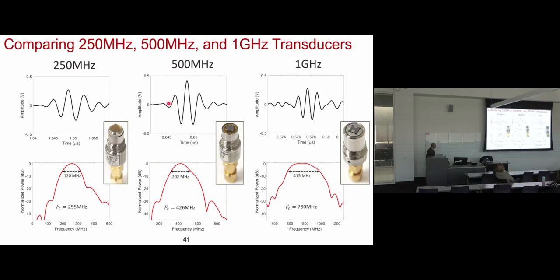So we have 3 different transducers at different center frequencies. If you want to understand this, they are essentially the magnification factor that you would have on an optical microscope, right? So you rotate. From left to right, you increase the spatial resolution by a factor of 2 every time you do that. And as you do that, the cost of the transducer increases, the sensitivity to vibration and temperature increases, the need for faster electronics increases. So basically, the higher the frequency, the harder it is to put together the system.